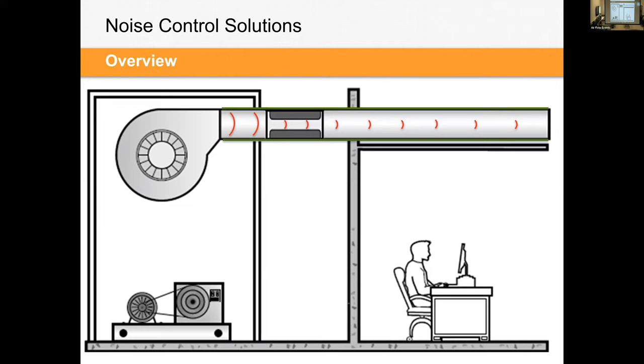And there were some standards that came out around that: if this wall is STC rated, like STC 50 rated, very high transmission loss, the penetration of the duct also needs to meet that equivalent STC rating. And that might be where you need a silencer of high construction class to be able to meet that.